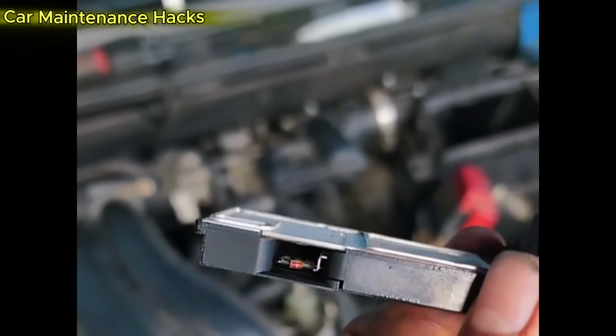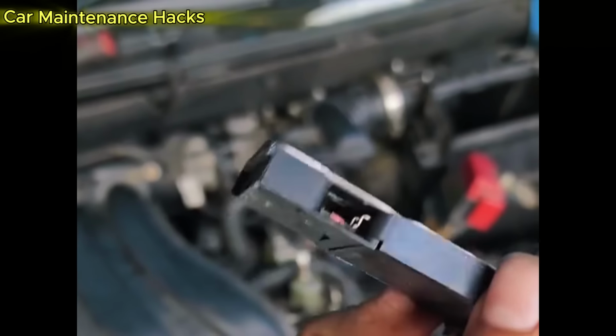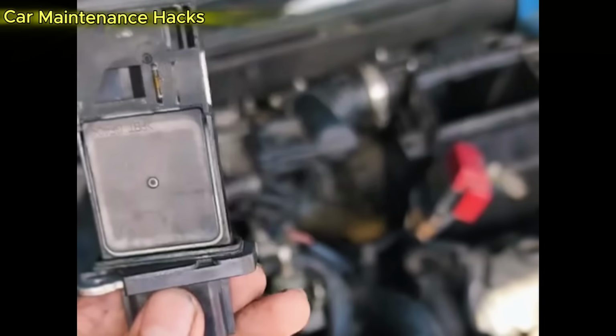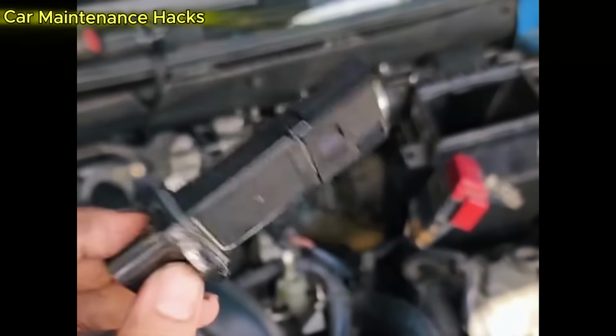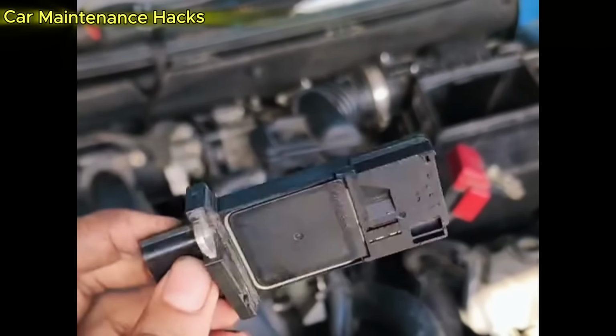Step 5: After spraying, place the sensor in a dry, ventilated area and let it air dry for 15 to 20 minutes. Never blow it with compressed air, never wipe it, and never reinstall it while still damp.